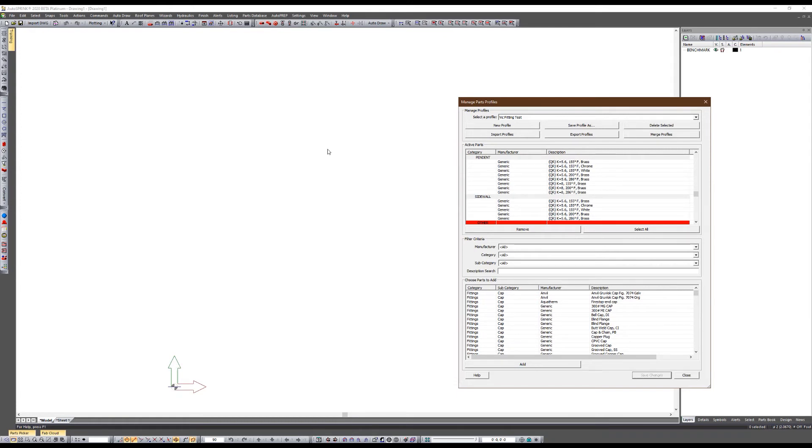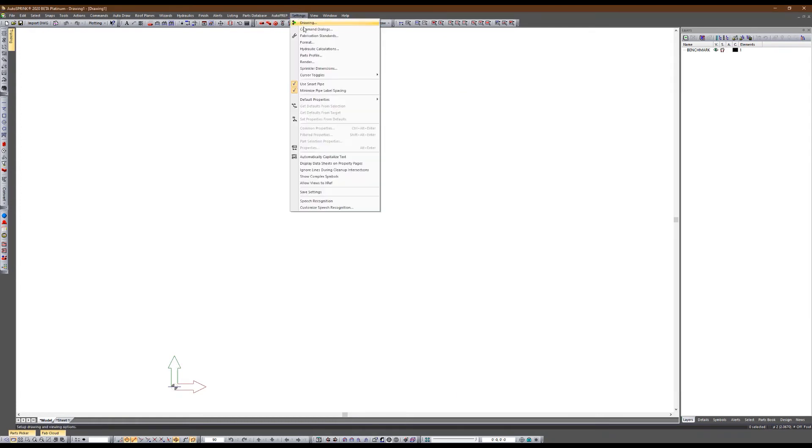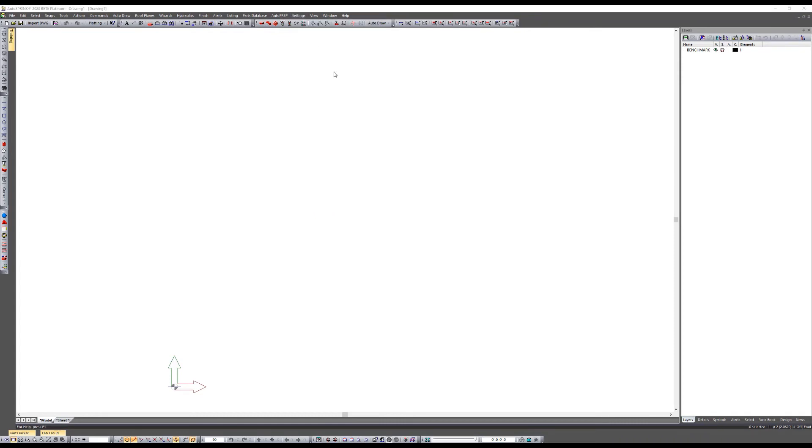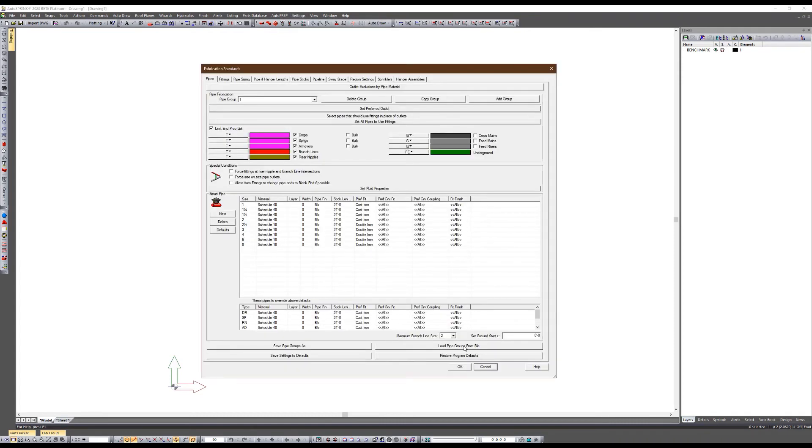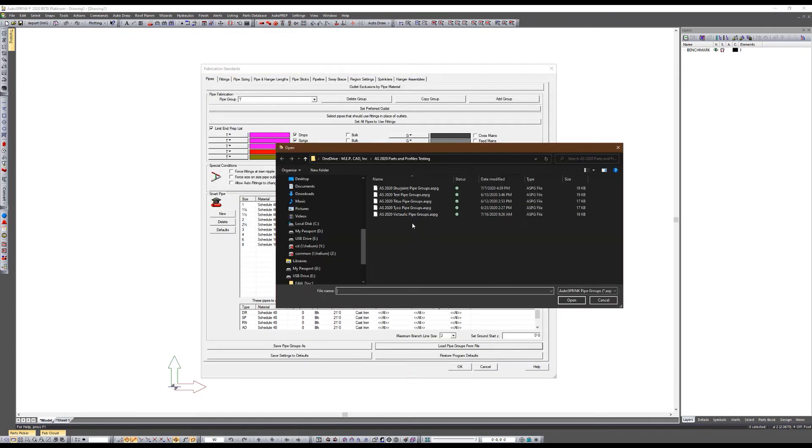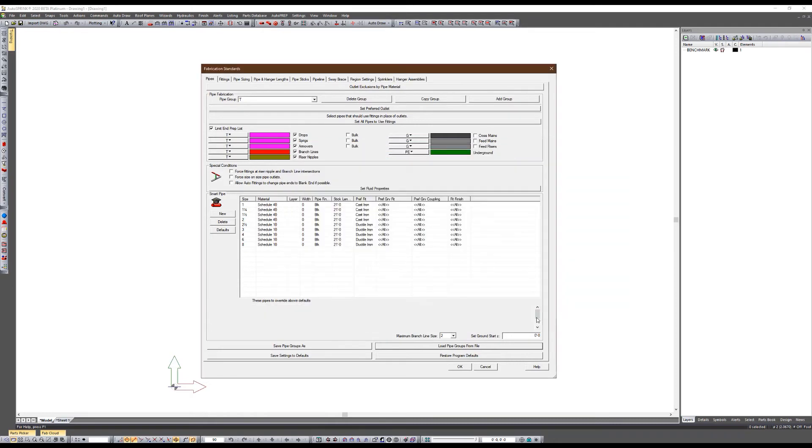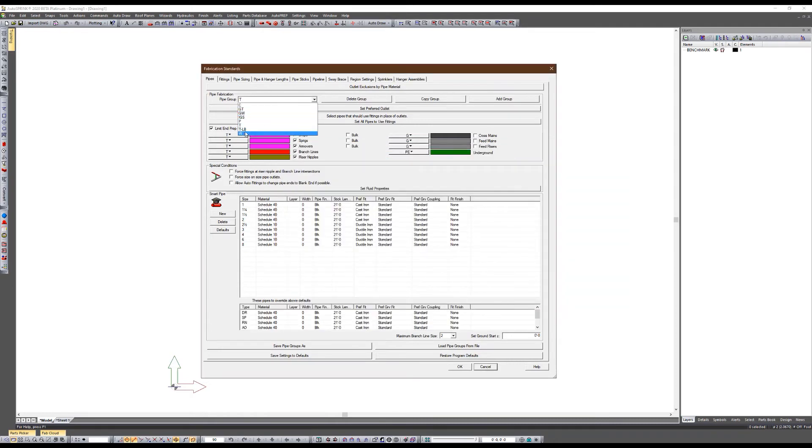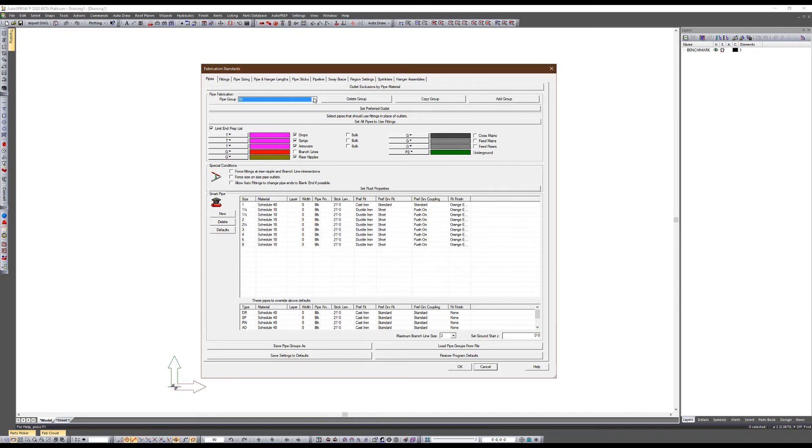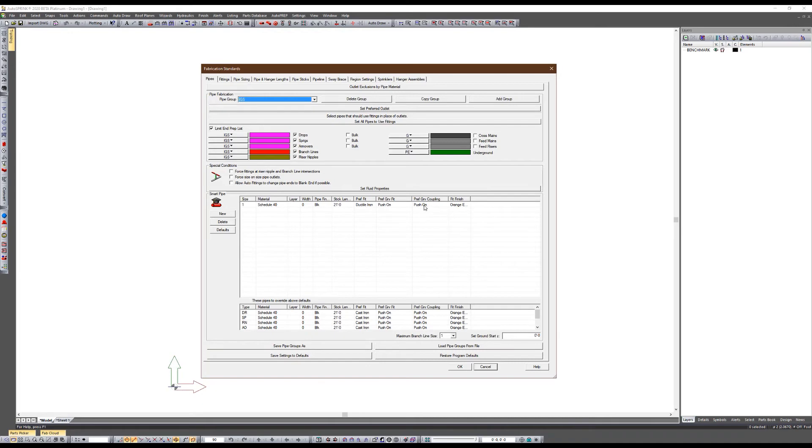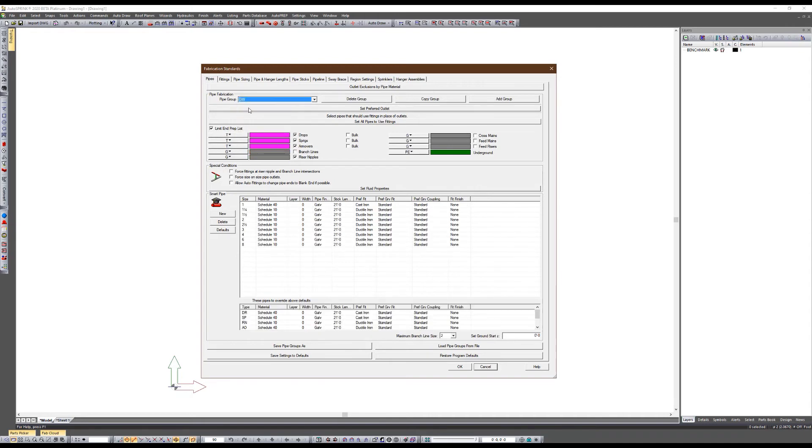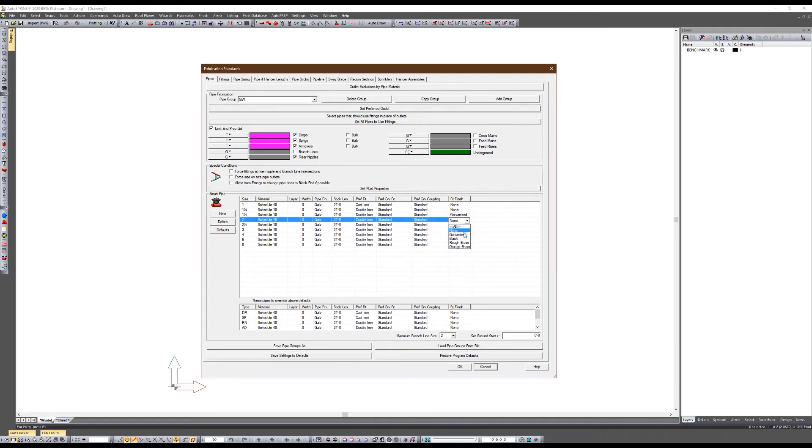Go back into fab standards, load pipe group. I'm going to load my Victaulic pipe groups. I can go to my welded, I've already set it to push on style grooved couplings, short radius grooved fittings, orange enamel finish for all of these. I've got my IGS group, it's just one inch push on fitting, push on coupling, same for my drop sprigs, riser nipples, arm overs. I want to use IGS for all of this. Even my galvanized, I changed everything. Pipe is galvanized. My fitting finish didn't carry over, I need to update.